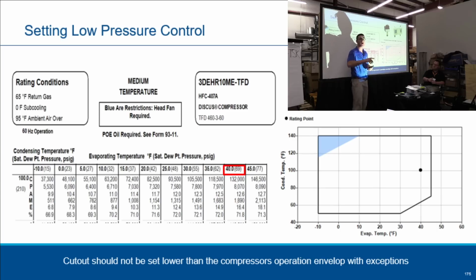But that's a really small amount of time, right? So that's the only case where you can do it from minus 10 to minus 20, because you're running at the borderline of that compressor. Right? Because if you just put it at minus 10, well, the compressor won't shut off, right? It'll just run.